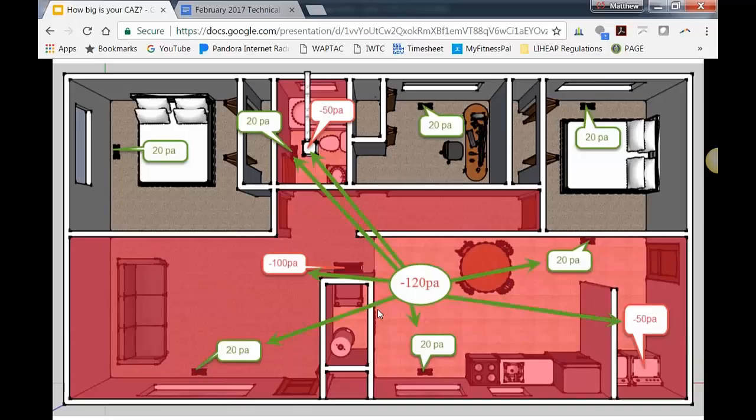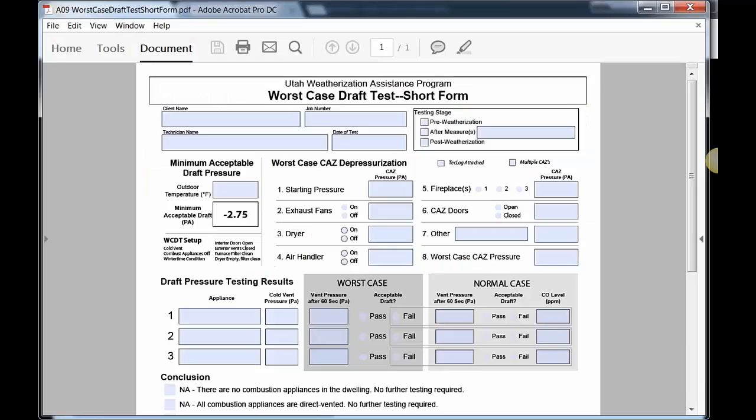So this was an example we ran into in the field, out working with some guys. The client had a swamp cooler in his bedroom that wasn't covered with anything. And of course that bedroom door would get closed and there's a supply run in there and the furnace is running. When that thing came on, all that supply air could go directly to the outdoors, and it was causing massive depressurization in the house.